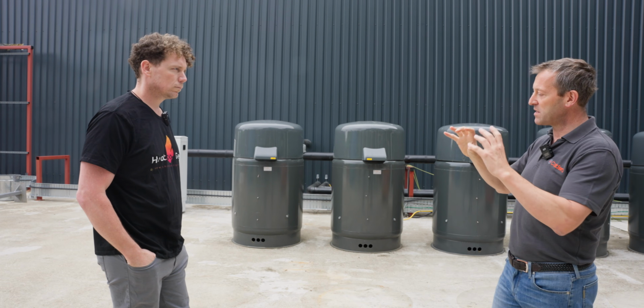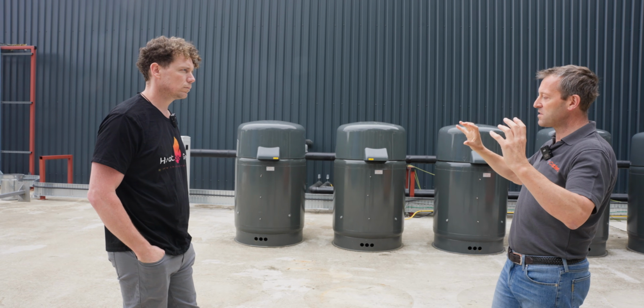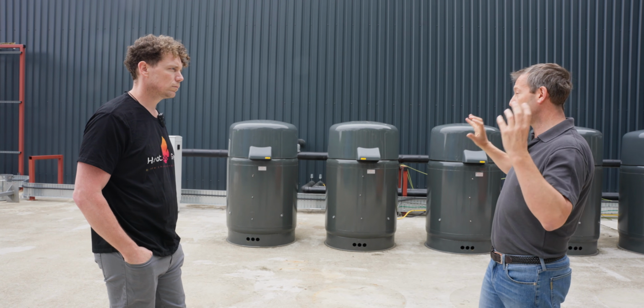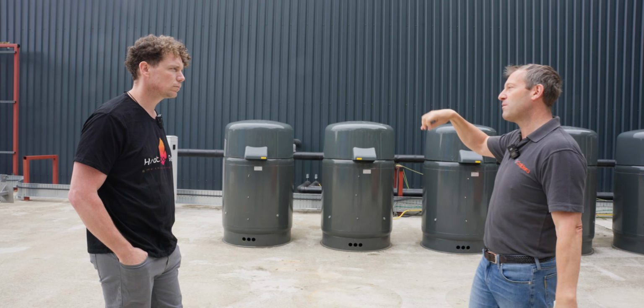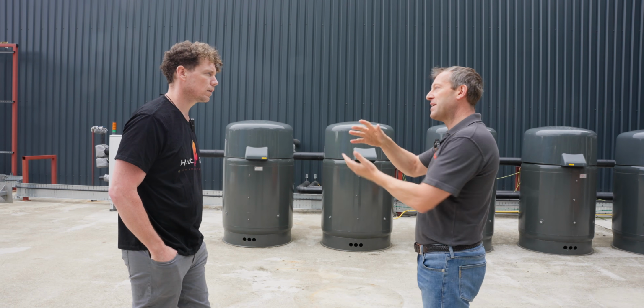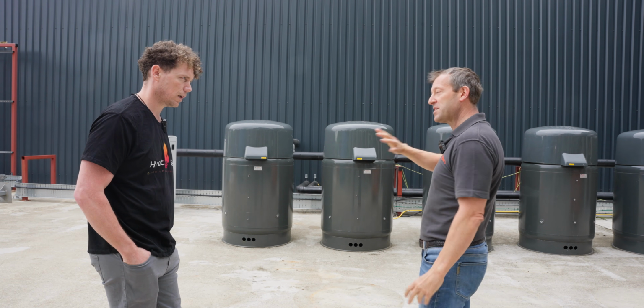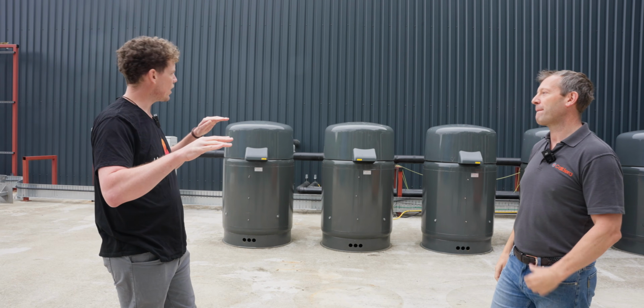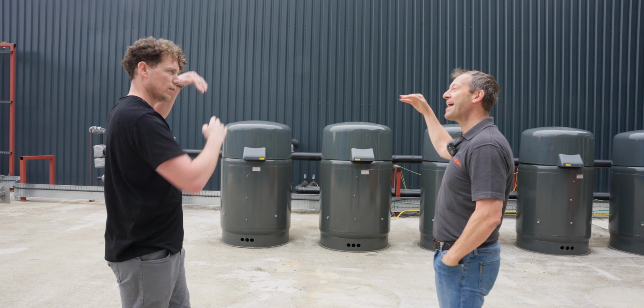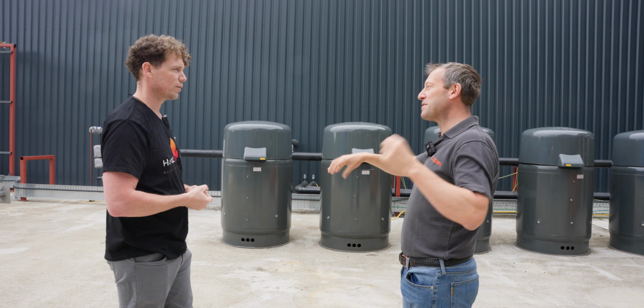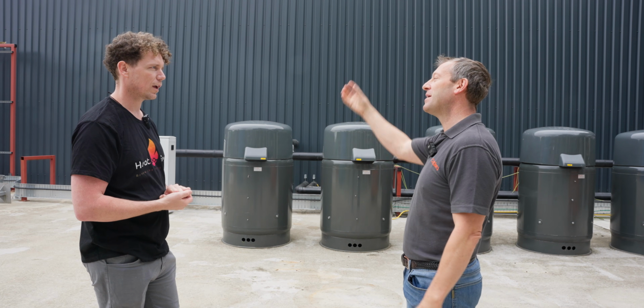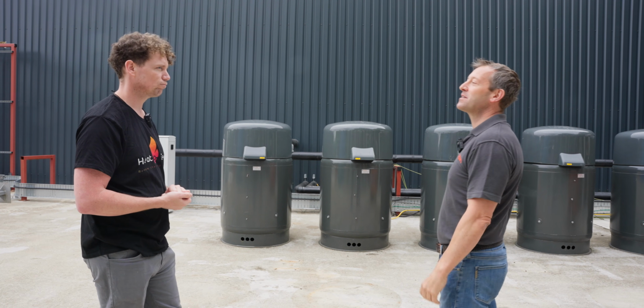The bigger problem is often with these steam pipes, where there's a little bit of cooling and liquid forms, so every now and then you have to manage the droplets because you don't want steam and water in the same pipe. That's part of the installation too, they angle things down, and at the lowest point you have a steam trap, which takes the water out and returns it to the condensate.